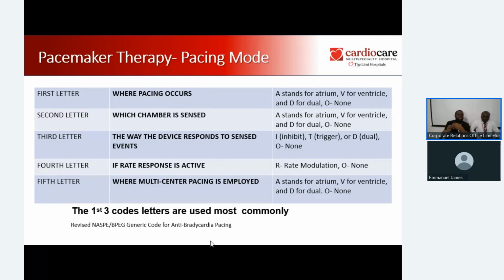Sometimes with people going for surgeries, we don't want the device to sense diathermy or a knife and assume that's a heartbeat, because if it assumes it's a heartbeat, the device will sit down and say, since the heart is beating, I don't need to work. In that case, the patient will pass on. So in that kind of case, we typically tell the device, don't bother about sensing, just pace continuously. If you are pacing the ventricle, V, and you are not sensing, that is O, and since nothing is going to be sensed, there's no response, that will be O, so that will be VOO.